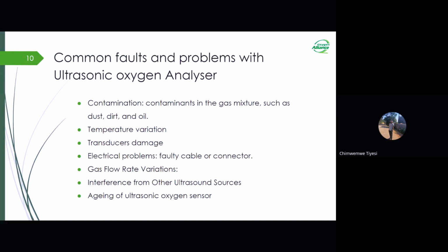While we are still here on issues affecting ultrasonic oxygen analyzers, another factor that can affect the accuracy of reading is gas flow rate variation. Variation in gas flow rates can affect the accuracy of the analyzer's readings. So what you can do is ensure that the gas flow is consistent and within the recommended range for oxygen analyzers.